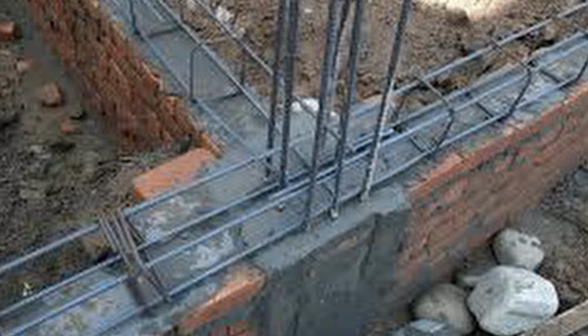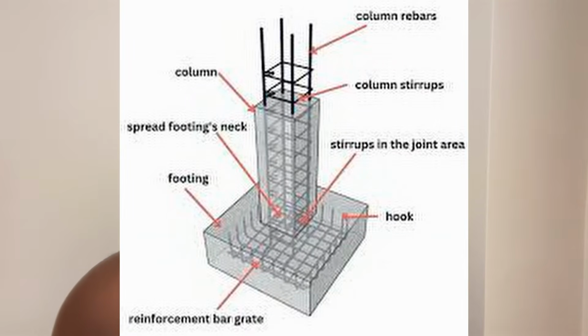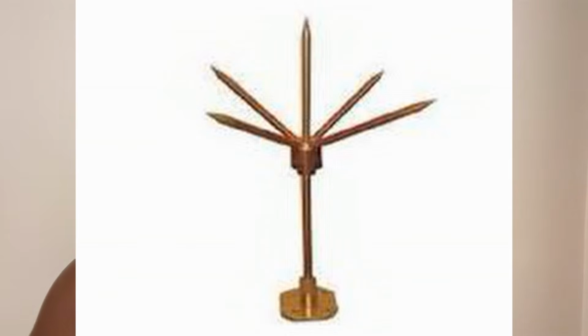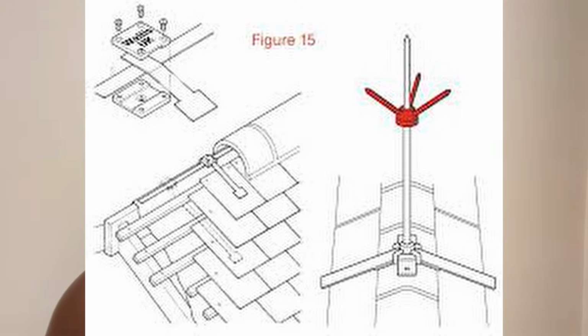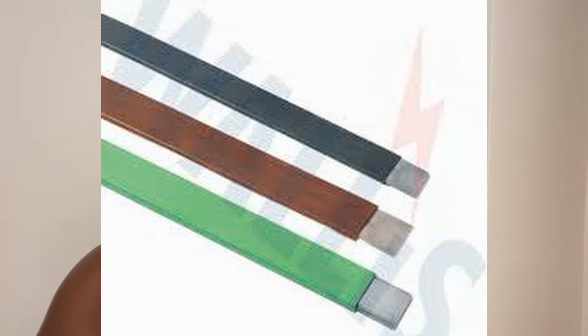Lightning protection integration. Lightning protection is not that separate from earthing in a sense, yeah? A proper lightning protection system includes the air termination or the lightning rod at roof level. In Ghana, some people call it the arrestor. Yeah, I'll show you a picture. It's above the roof. It's like an aerial spike that collects the charges when there's lightning in the area. Okay. Then you have a down conductor, which is either copper or aluminium. I would recommend copper. It's a 25 by 3 mil copper tape. I would recommend the one that has got insulation around it, not the bare copper.